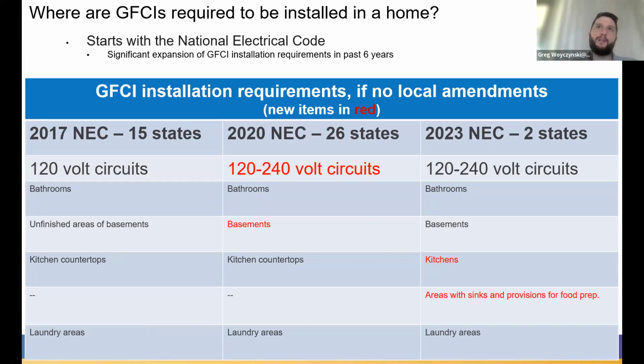So we've seen significant changes in how to answer this question over the past few years. If we start by looking at the 2017 NEC, which is effective in about 15 states right now, we see that GFCIs focus on places like bathrooms, kitchen countertops, those kinds of places. Then in the 2020 NEC, because of a really big push from GFCI manufacturers, we see that GFCIs are being required in not just 120 volt circuits, but also on 240 volt circuits. So if you live in a state where the state electrical code has adopted the 2020 NEC without GFCI amendments, you now have to connect, for example, wall ovens, dryers, and 240 volt air conditioners to GFCIs if they're in certain locations.